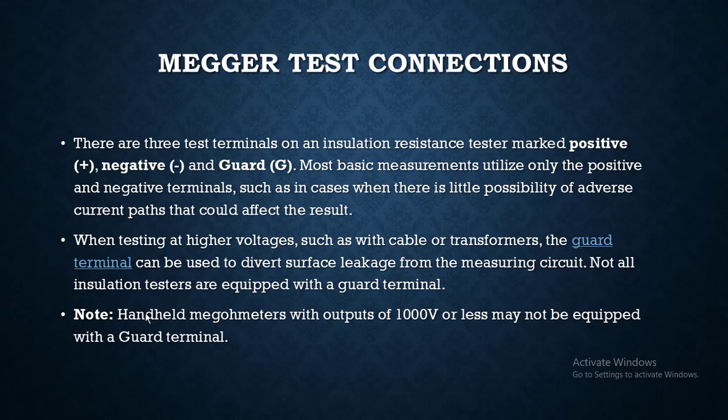Let's discuss some basic information about megger test connections and the terminals available in the megger. There are three test terminals on an insulation tester: positive, negative, and the guard. Most basic measurements utilize only the positive and negative terminals, such as in cases when there is little possibility of adverse current paths that could affect the results.